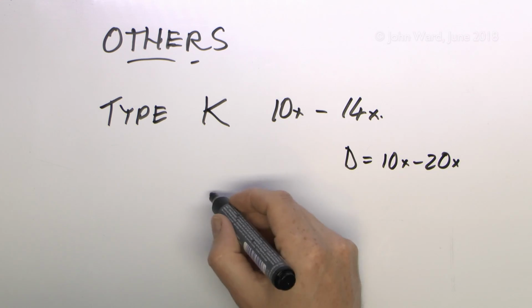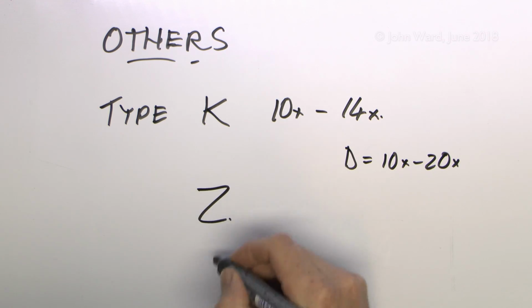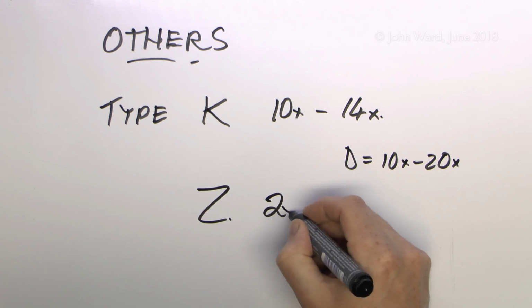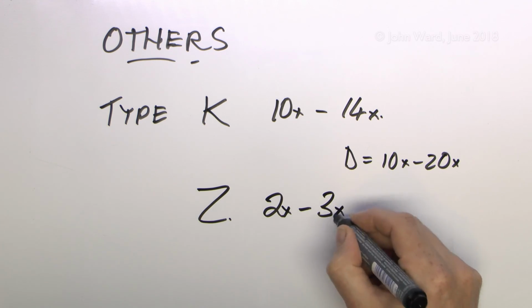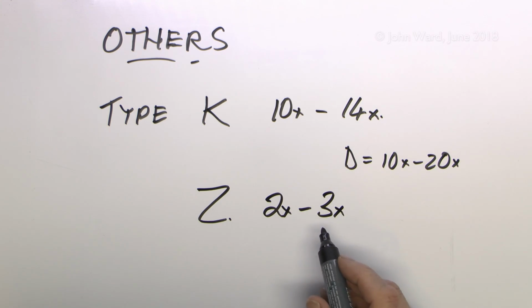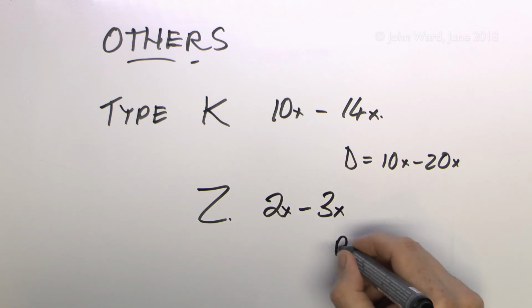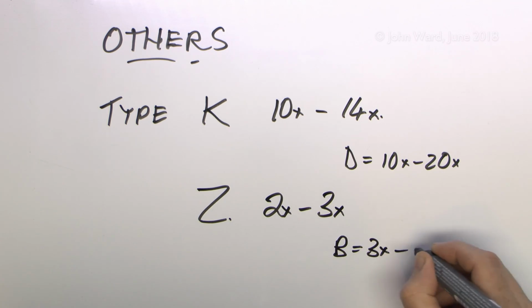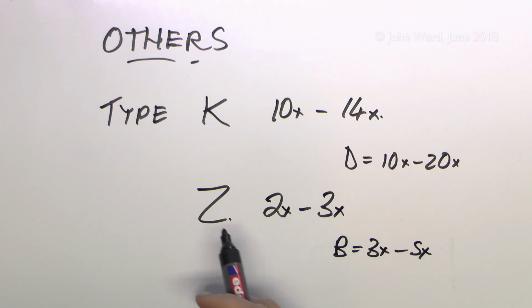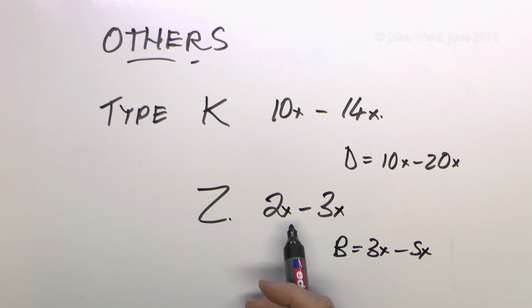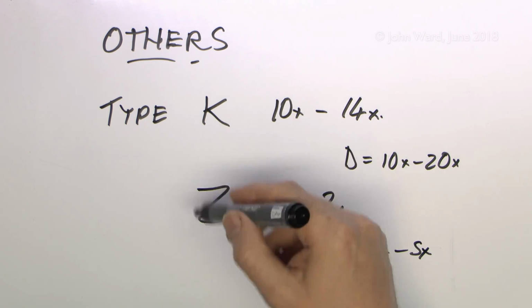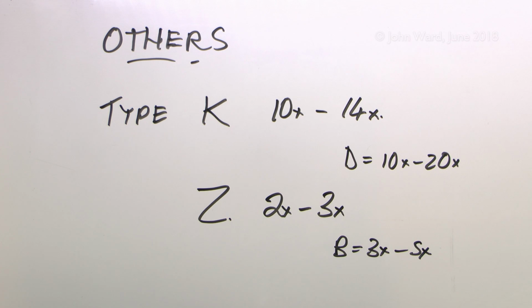And then the other one, which again is a fairly uncommon type, is the Type Z, and this actually trips between 2 times and 3 times the current. And again, this is actually below the rating of the Type B, as we saw the B before was 3 to 5. So this would be the kind of thing you would use on a circuit that either had a very high impedance, and therefore you only need a very small current to trip the thing. Typically used on things like control circuits and that sort of thing, but not a particularly common item, but nevertheless these things do exist and do have usage in certain applications.